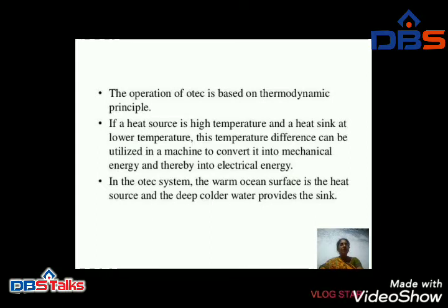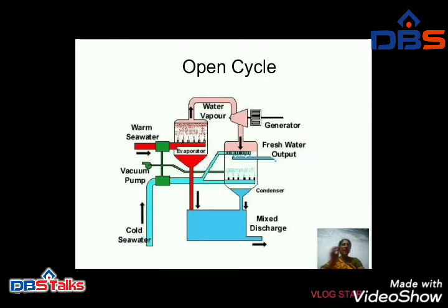So the main thing is that this principle works as a Rankine cycle. The warm water is used to evaporate the working fluid like ammonia or some other refrigerant, and this evaporated fluid expands in a low pressure turbine, which is coupled with the generator to produce electricity.